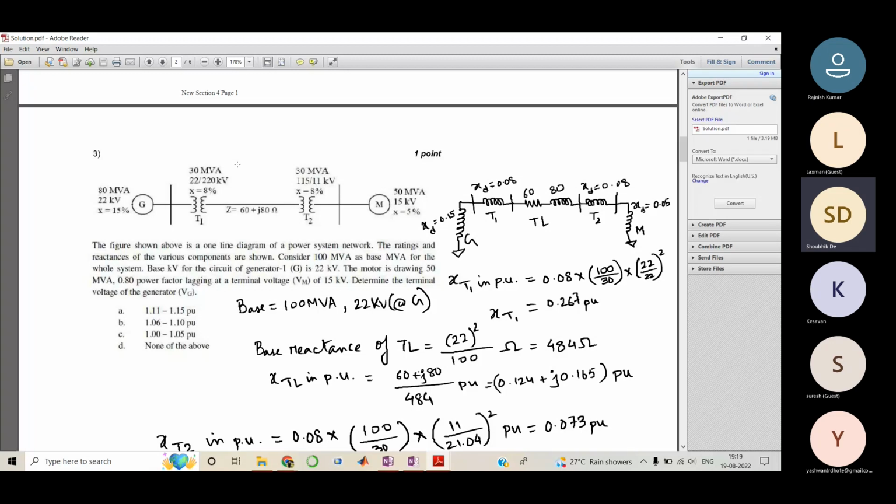No, no, no. All these components are three phase only, because 30 MVA you can't get single phase, right? So, as far as I know, any component with a voltage rating above 5 kV becomes three phase. So, all of these are three phase components.